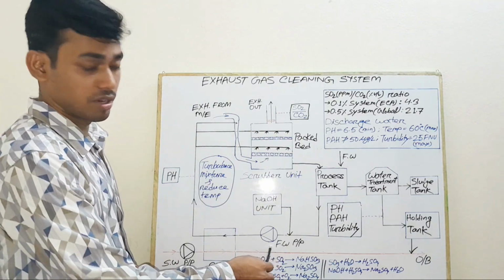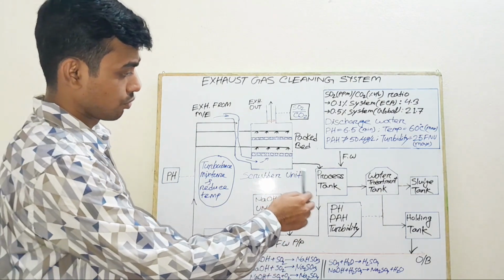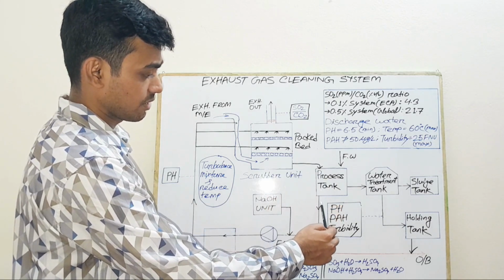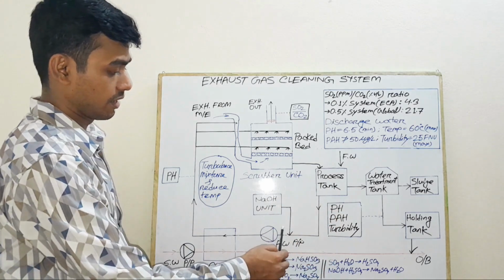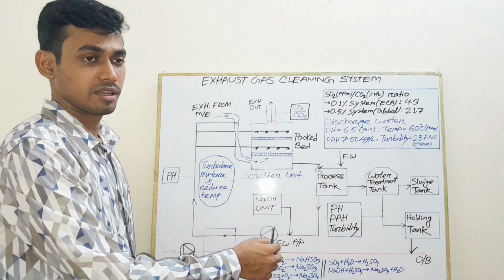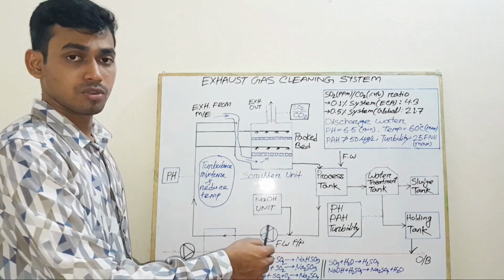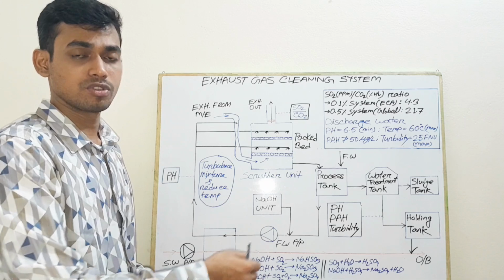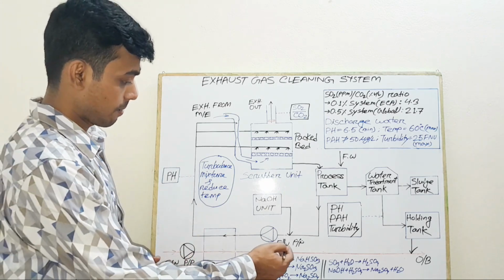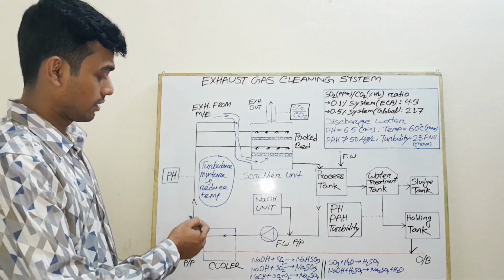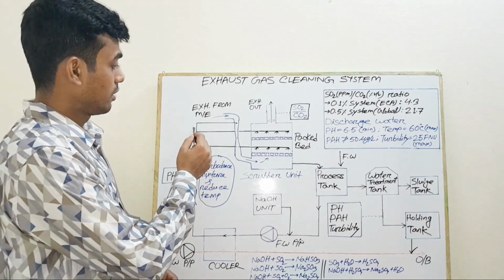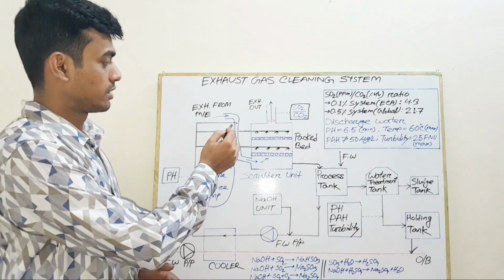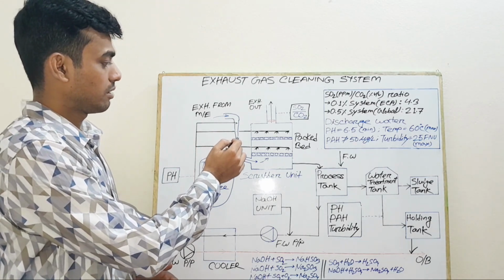See the fresh water circulating pump. So through the process tank, fresh water from the scrubber tower is coming here through the process tank. Fresh water is coming here, and here sodium hydroxide is added to give the alkalinity. The alkalinity is used to neutralize the wash water. That means sodium hydroxide is used to neutralize the wash water. Then fresh water is coming here, and here pH is sensed, and the first line, the branch, you can see this fresh water is injected through the spray into the venturi meter.